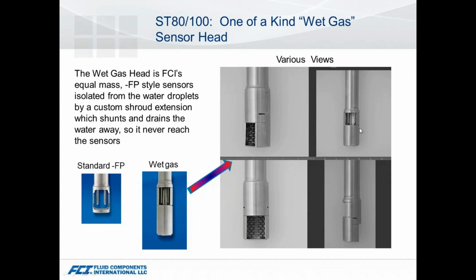And then you look on the right, upper right, that's the outlet of the sensor, and there's actually a small barrier between the inlet and the outlet side, with a very small gap, and that helps knock out more moisture from your process gas. Then you can see the basic configuration, inlet outlet here down on the lower right.